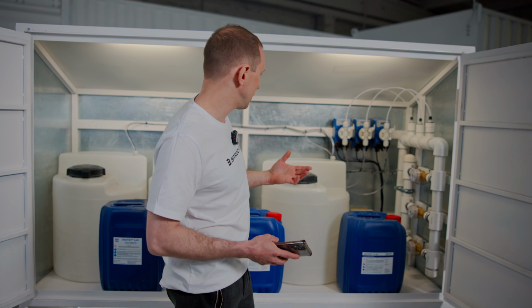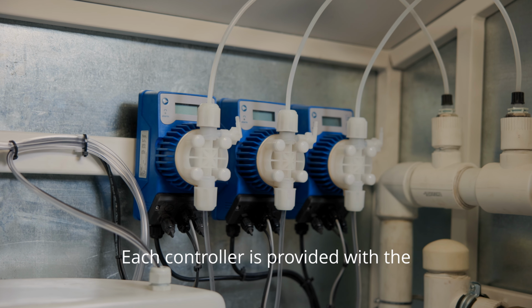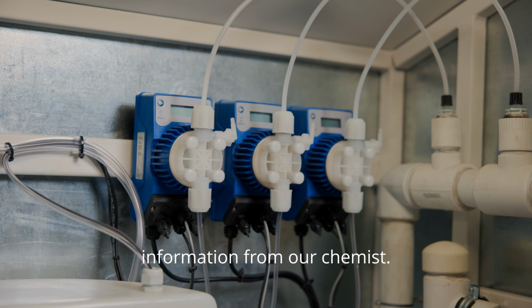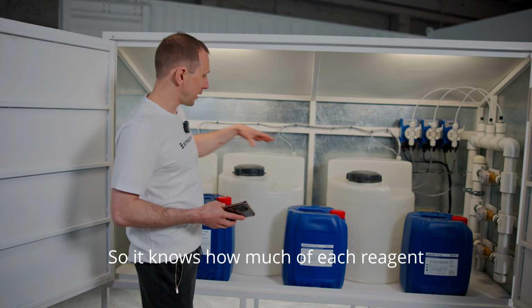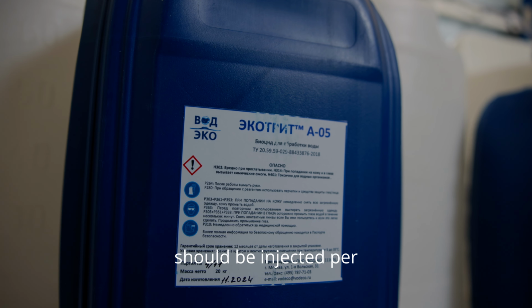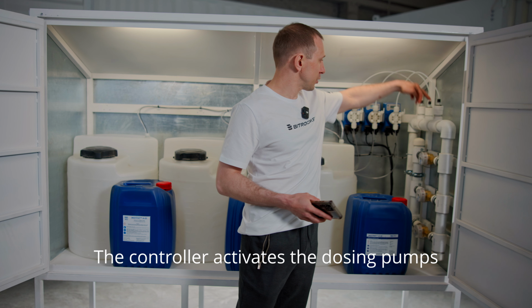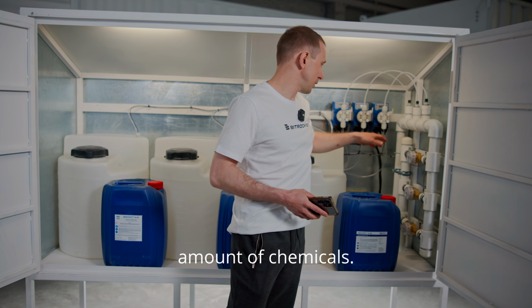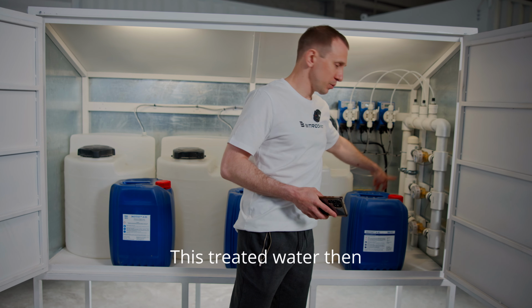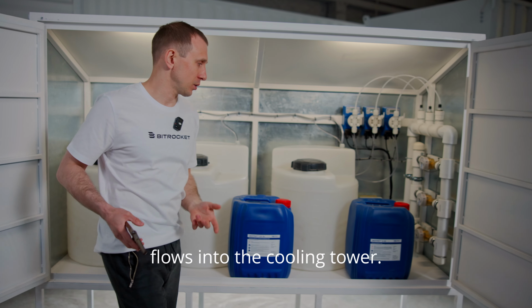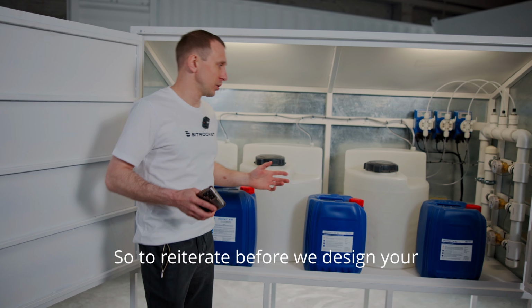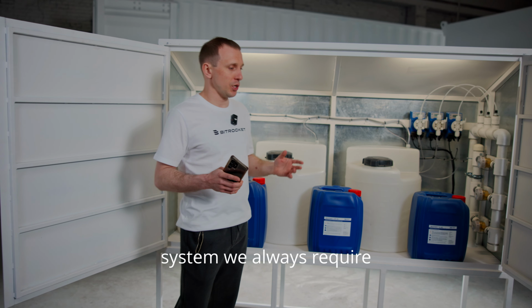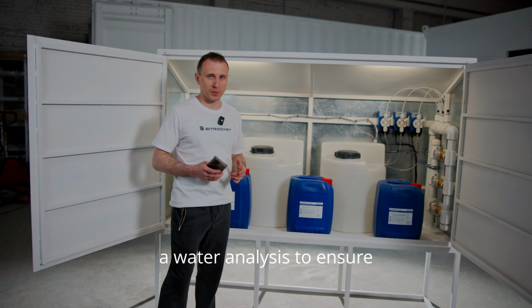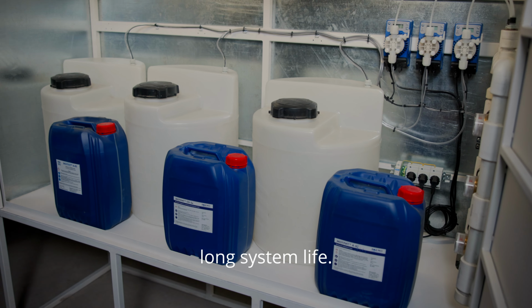the system. Each controller is provided with the information from our chemist, so it knows how much of each reagent should be injected per liter of incoming water. The controller activates the dosing pumps to inject the correct amount of chemicals. This treated water then flows into the cooling tower. So, to reiterate, before we design your system, we always require a water analysis to ensure long system life.